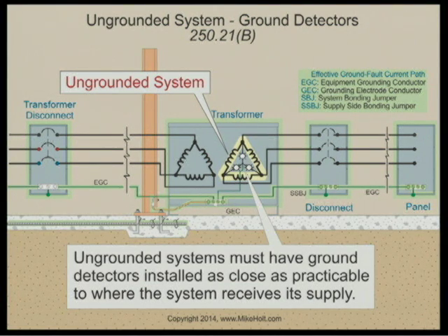The code requires that if you do have an ungrounded system, you have some kind of ground detectors. That's 250.21(B). And here's a simple way of doing it: taking 3 light bulbs and connecting one to each of the phases. I put a 240 volt bulb here because of that voltage.